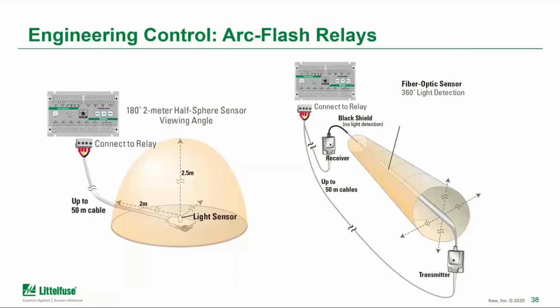And for those that are not familiar with the light sensors or how they work, there are two different types of sensors you can see on the market. There are single point sensors, or there are fiber optic sensors. That allows them to be installed in many different kinds of cabinets, or the fiber optic sensor can be placed in bus bar chambers or other difficult cabinets where there's a lot of different pieces of equipment. So with a relatively low number of components, it can provide arc detection in most types of equipment.